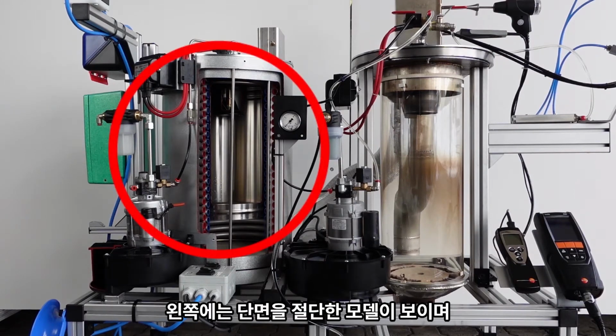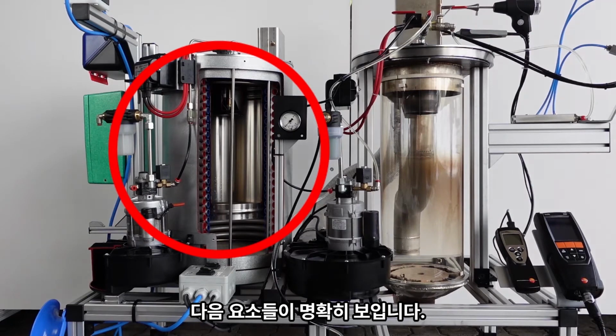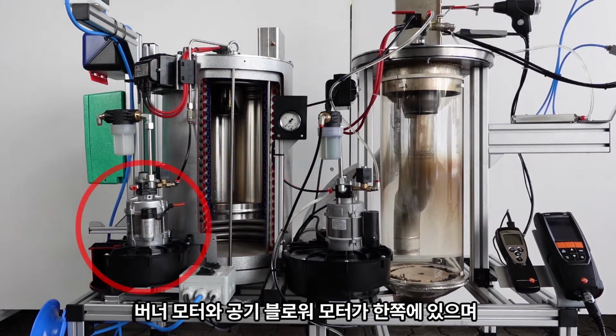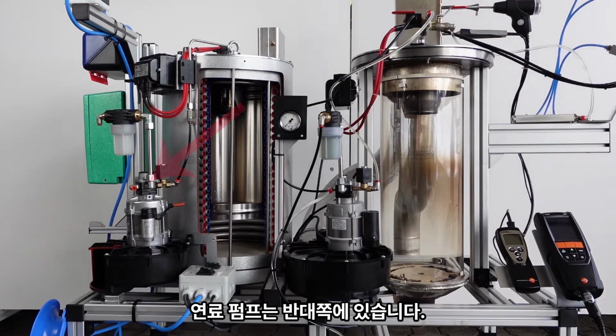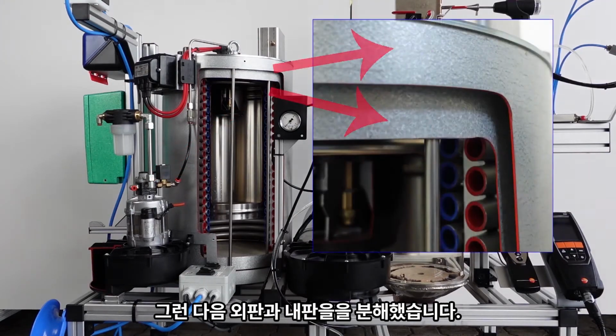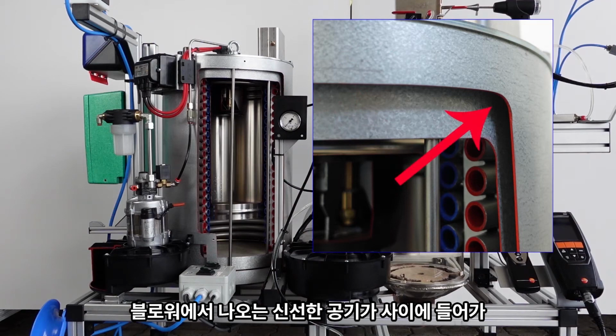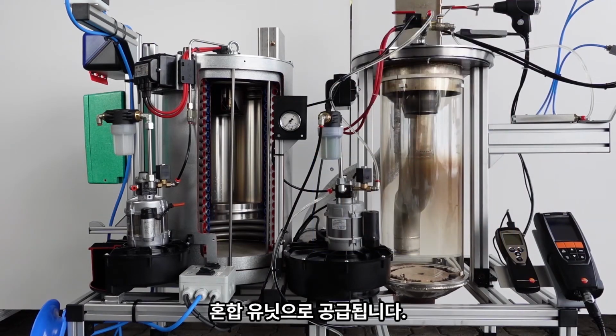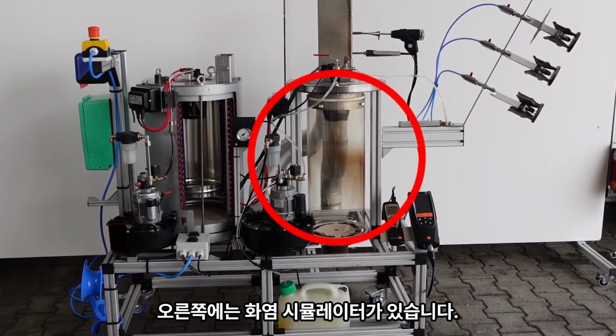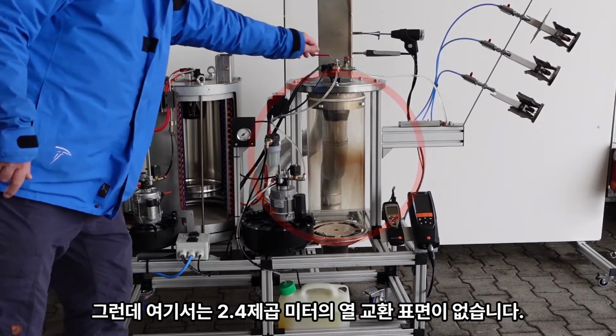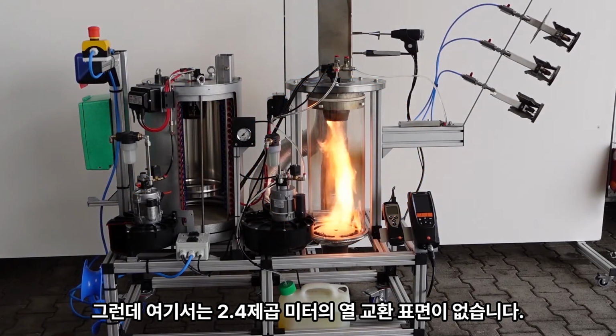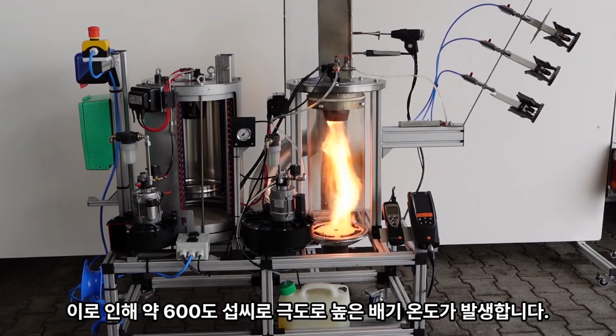On the left side, we see the cutaway model, where the following elements are clearly visible: the heating coil, the burner motor with the air blower motor on one side and the fuel pump on the other side. Then the inner mantle and outer mantle, and it is in between these that the fresh air from the blower is fed to the mixing unit. On the right, we have the flame simulator, where the same masses are found as in the real heat exchanger. The difference is that in the flame simulator, we do not have a heat exchange surface of 2.4 square meters. This explains the extremely high outlet temperatures of approximately 600 degrees Celsius.